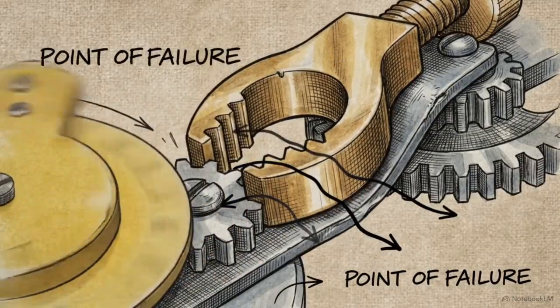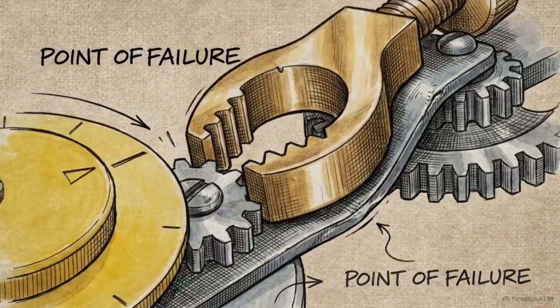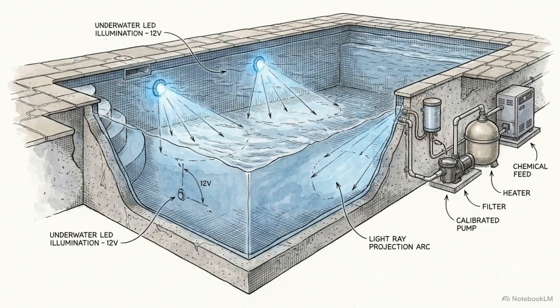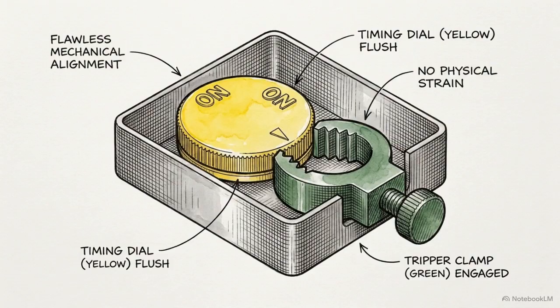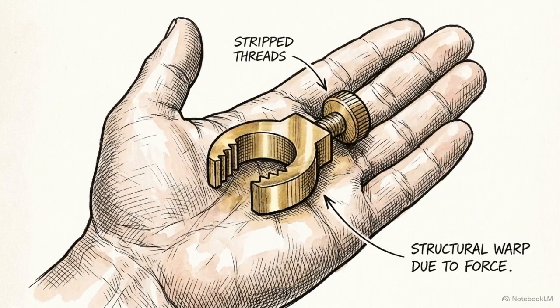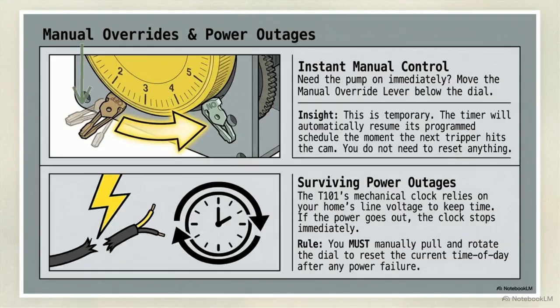Too tight, and you will bend the tripper and jam the clock mechanism completely. Perfect calibration and precise tripper tension dictate how this hardware operates. Lock them down correctly, and the system will run cleanly for years. Over-tighten them, and it will jam in a week. To turn equipment on manually, push the override lever. The timer automatically resumes its cycle when the next tripper passes.